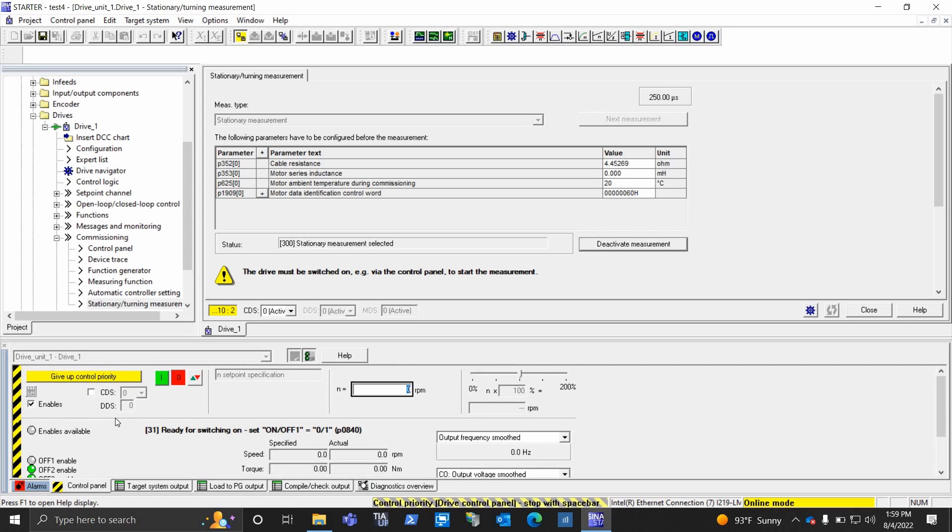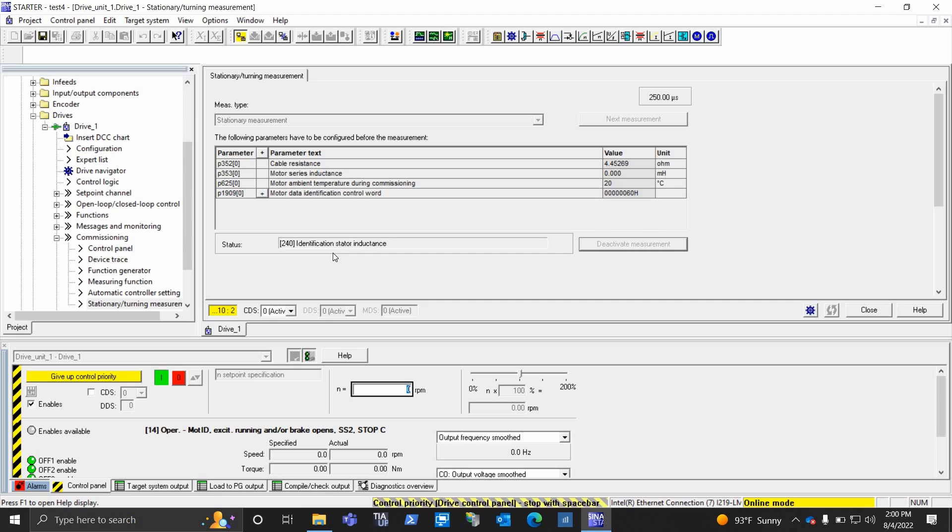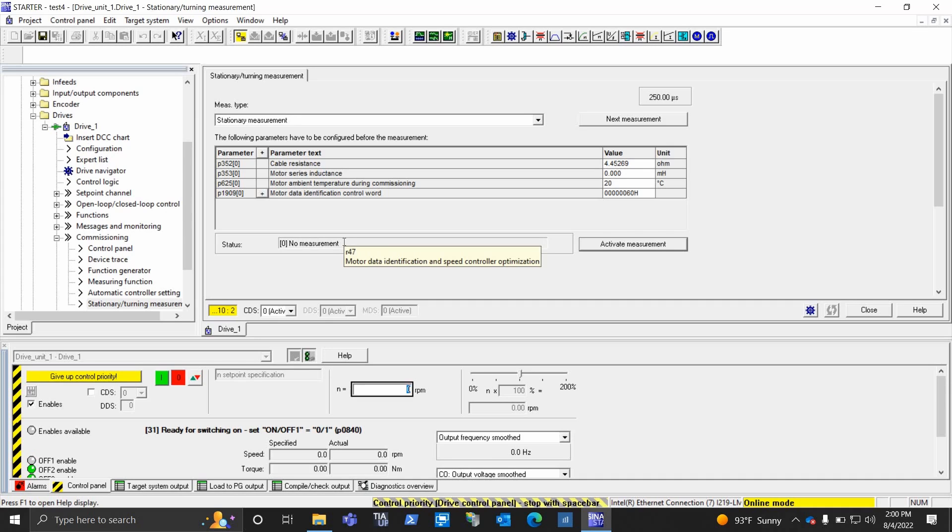Now that bypasses any interlocks or any safeties that you may have. So if there's something that has to run before this motor spins, make sure you have that taken care of. I hit the drive on, it starts its tune. And then in the little status, it actually tells you all the details of what part of its tune it's actually running at that point. Not really important unless it fails the tune and you can take note at what point it bombed out on you. It goes to no measurement. There's no faults or alarms that'll be flashing there if there is, but there are none, so that was successful.